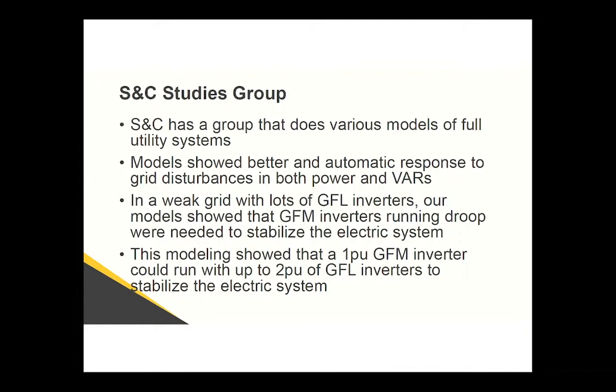So that showed that we should really be looking at more grid forming inverters on the system. And in one case, we had a lot of existing grid following inverters, and we looked at adding grid forming inverters to see, for a pure inverter mix, how many grid forming inverters we would need to stabilize it. And we ended up with about 1 per unit of grid forming inverter would handle 2 per unit of grid following inverters.